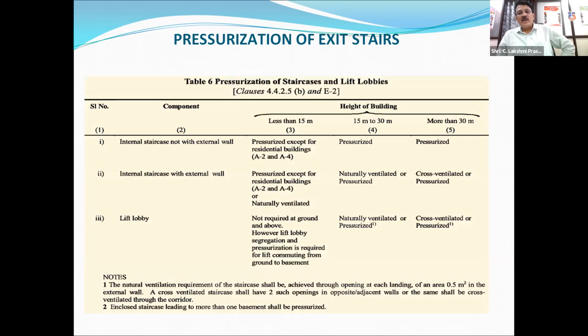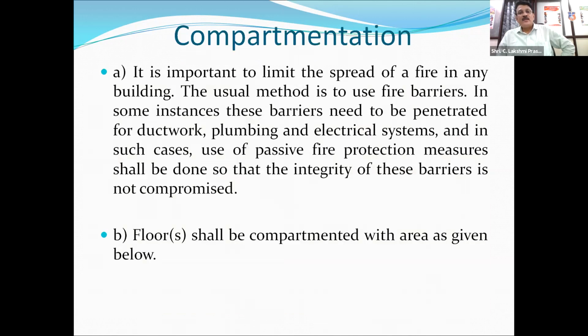Natural ventilation is allowed only for buildings up to 30 meters. Above that, it has to be pressurized. Then compartmentation is dividing the whole area into smaller areas to prevent the spread of the fire. That is also where you, structural engineers, play a very important role in ensuring that compartments are provided as per the code. They have given the various areas for various occupancies.